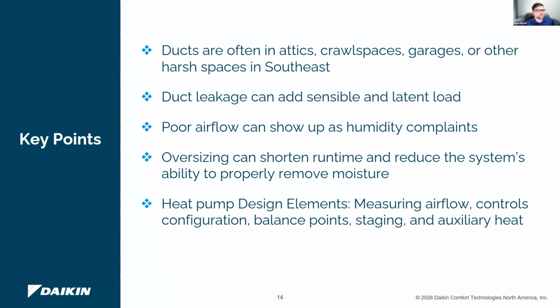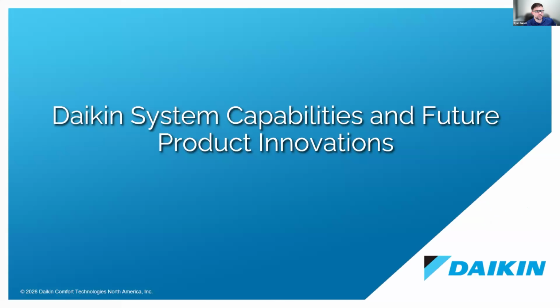Key points: ducts are often in attics and crawl spaces, literally the worst places you could ever want them. Duct leakage adds sensible and latent load, and poor airflow can show up as humidity complaints. Oversizing and installation faults end up compounding. So measuring airflow, controls configuration, balance points, staging, and auxiliary heat are critical pieces to making sure our systems are performing correctly.